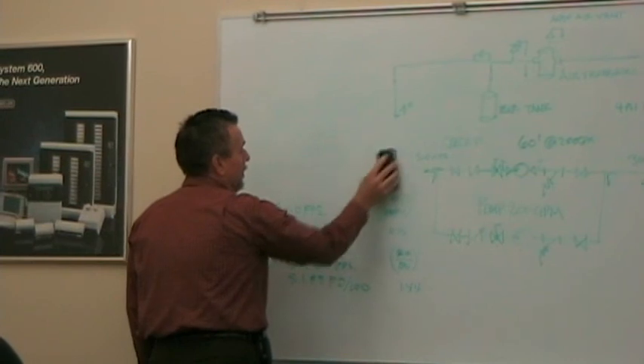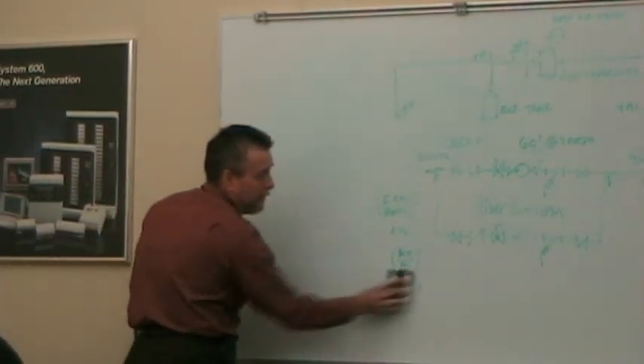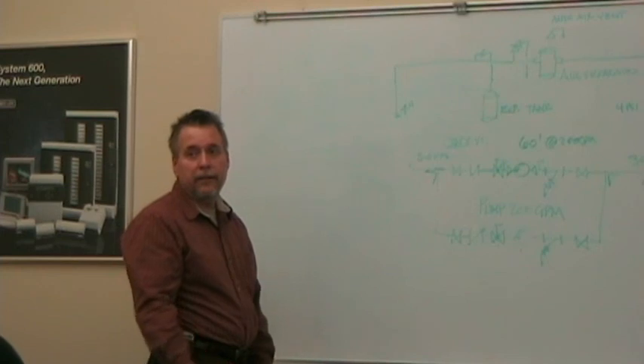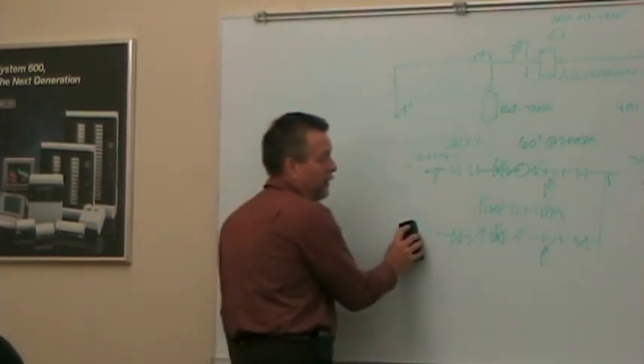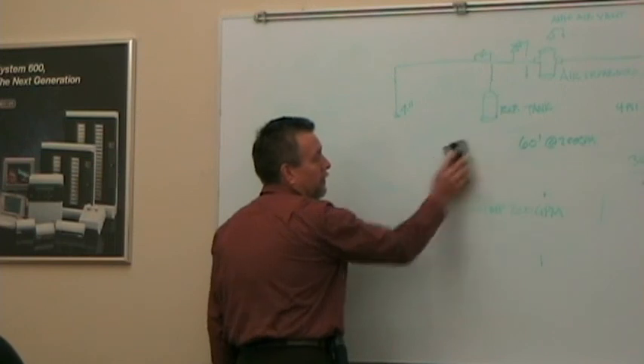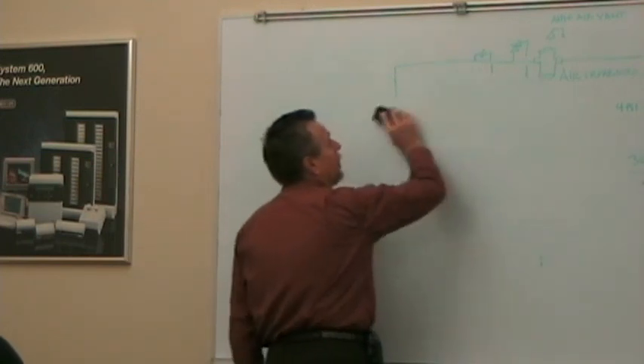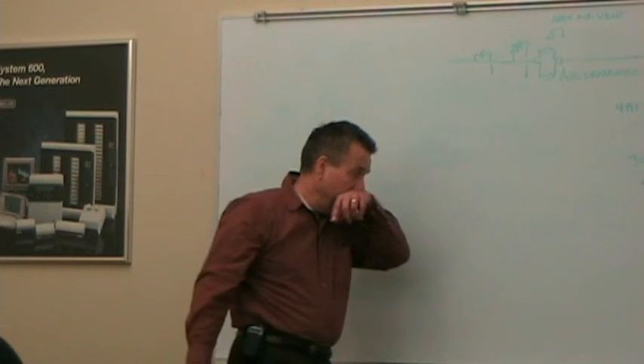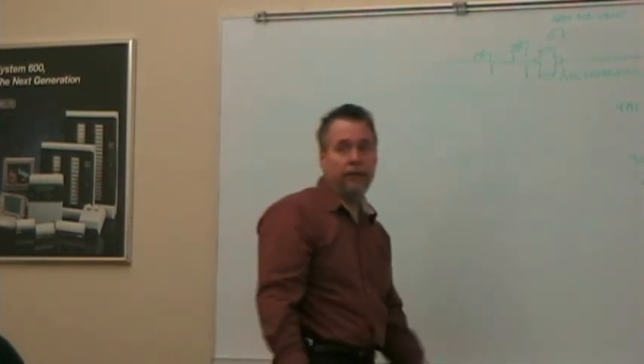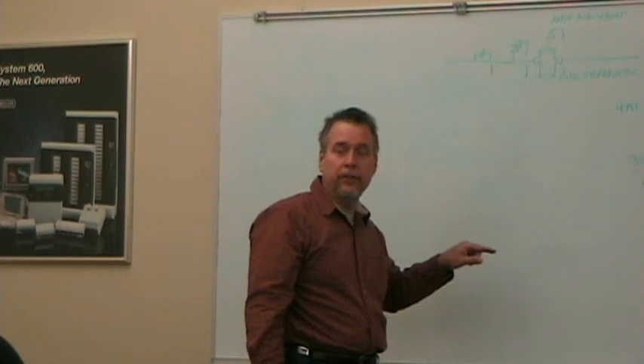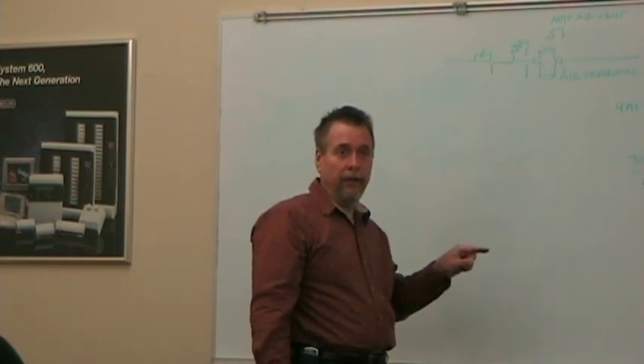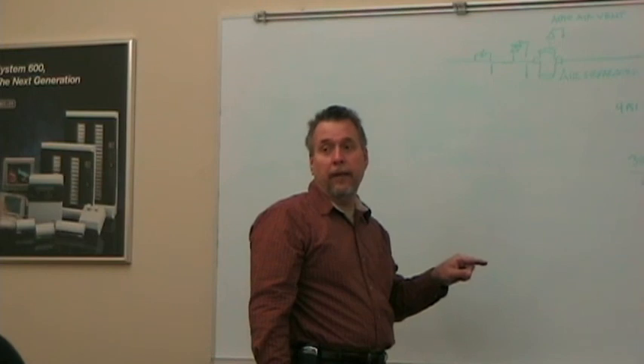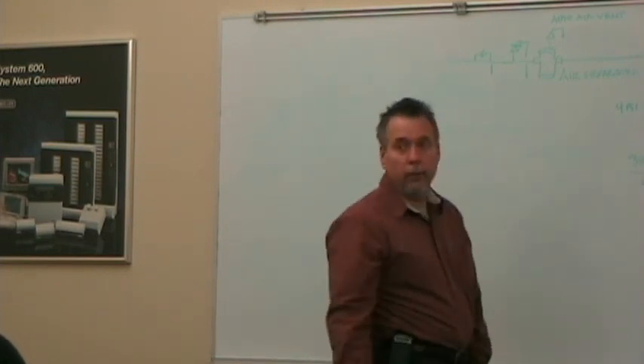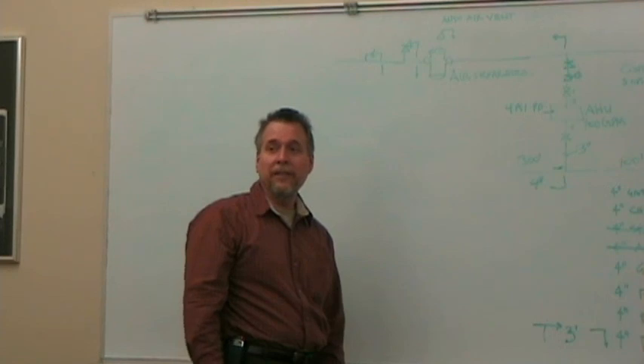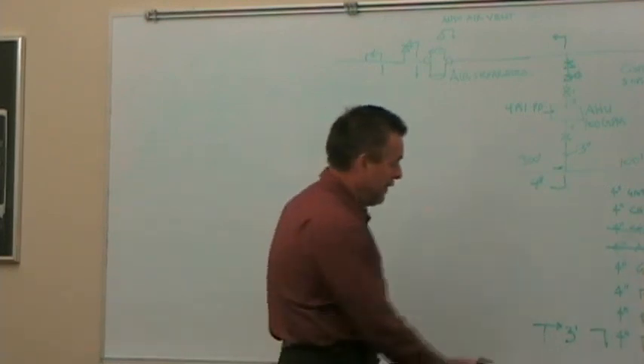How often do you see a condenser water pump running in a vacuum? 20% of the time. Okay. I know Victor buildings does. Yeah. You've got not big enough pipe, cooling tower's not above the pump enough. Operating in a vacuum is not necessarily a bad deal if you compare it to, and I'll show you on the net positive suction curve of your pump. So operating at a few feet of vacuum, it may not necessarily be that bad a deal. Operating at 10, 20 feet of vacuum, a pump's going to make a lot of noise.